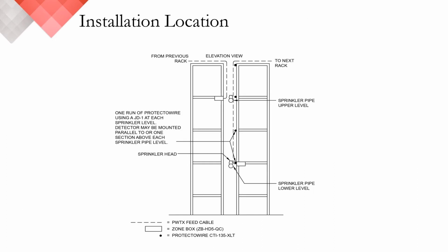On your screen in front of you, we have an elevation view of a racking system. Now, this can be considered an oversimplification, so let's discuss it. For in-rack detector installations, the Protectowire company always recommends installing the detector in the longitudinal flue space and attaching it to the horizontal load beam at each sprinkler level. The purpose of suggesting this location is to minimize any risk of mechanical damage from incoming forklifts or other items.